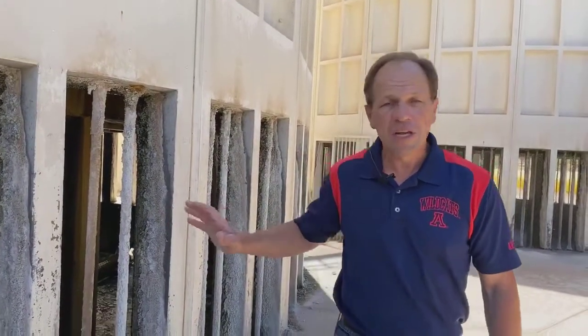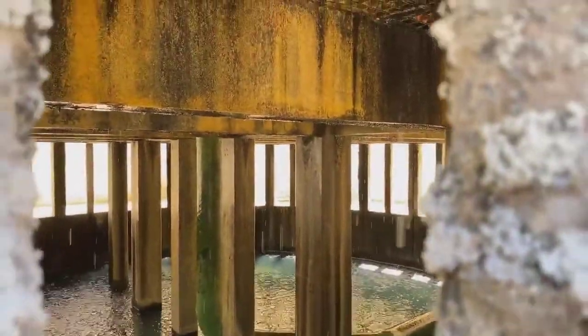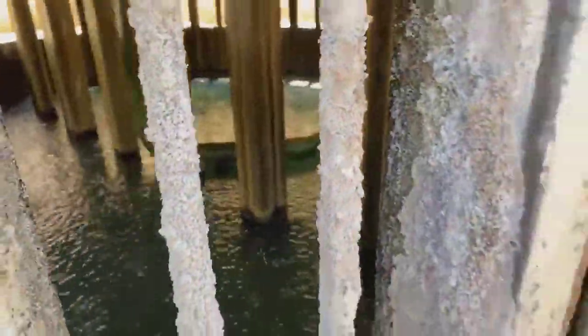We've been able to almost completely eliminate the mechanical chiller and use these cooling towers and the evaporative process to cool the air inside Biosphere 2. These cooling towers are pretty unique. If any of you have been to a central plant anywhere else, most of the fill used in cooling towers is either wood or plastic. These are ceramic, which makes them really unique — they're very resistant and don't decay or break down like those other materials. What you're looking at here is the basin. This tower is called an updraft tower. There's a big fan at the top. We've turned this one off because it's really loud. What happens is the water is pumped to the top of the tower and allowed to flow down — it almost looks like a rain shower.